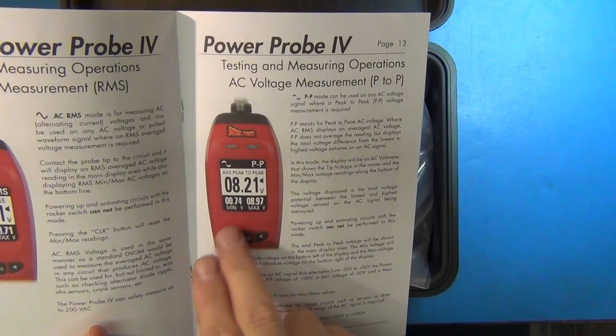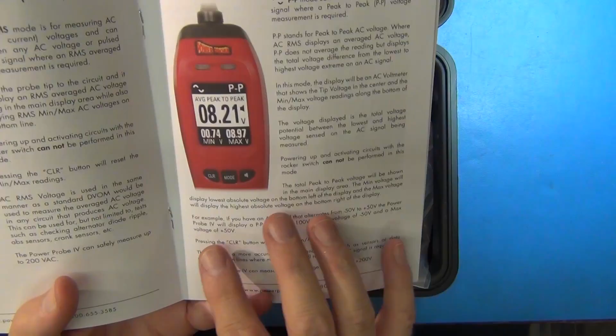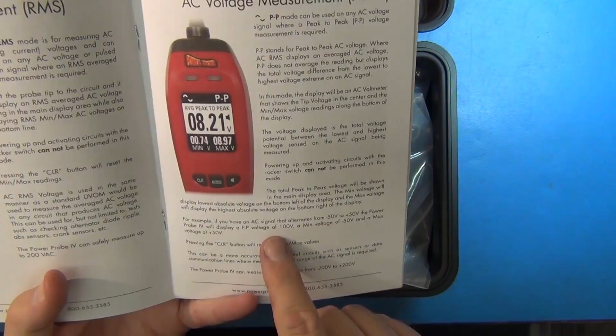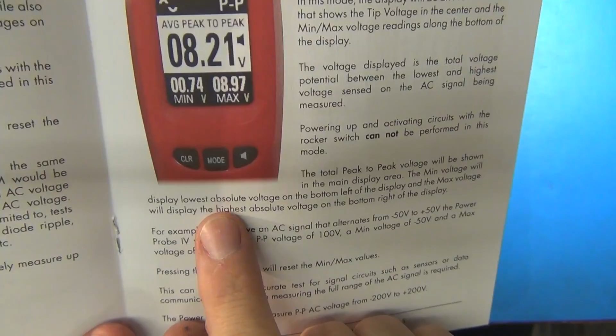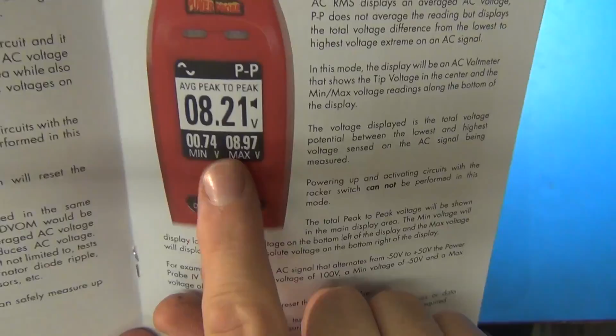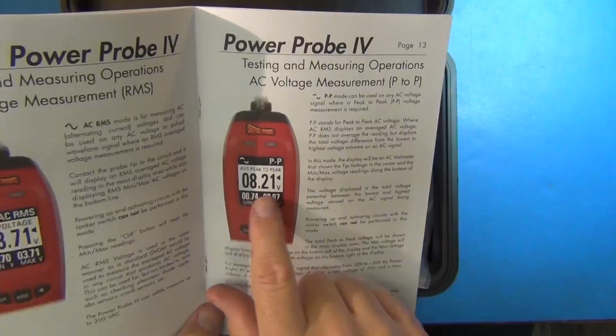What's interesting is it shows the AC signal as, for example, minus 50 to plus 50, even though this thing can go minus 200 to plus 200 volts. They're just saying, as an example, if you were reading 100 volts and it was minus 50 to 50, you'd see 100 up here, minus 50 here, and plus 50 here. But down here it shows the lowest absolute voltage and then the highest absolute voltage — there's not going to be a negative sign from what they're showing, so you have to be careful to catch that the difference is showing you that.